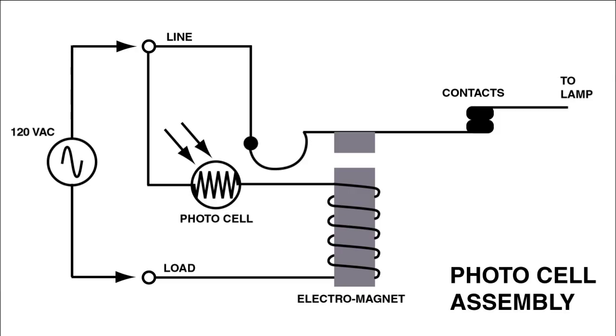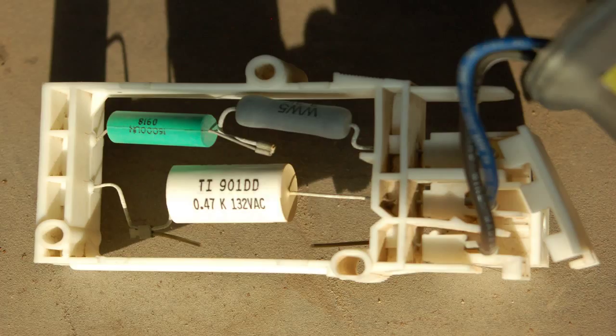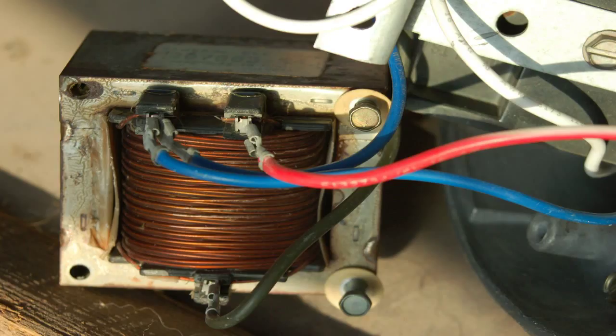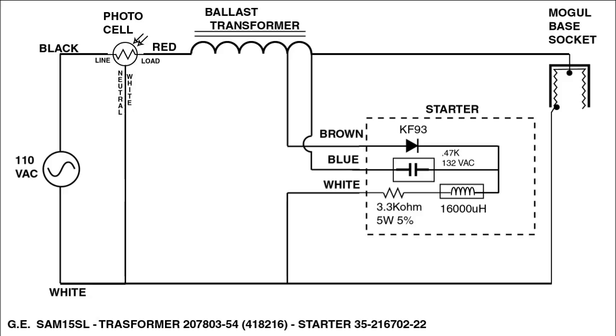If you can eliminate the photocell, then try the starter if you can get one. Most vendors just want to sell you a new fixture, but the starter can be acquired if you dig a little. If the starter doesn't fix it, and you haven't found any broken wires or bad connections in the process, then you can try the transformer. Again, it's not easily available, and they seldom fail. When all else fails, you'll have to bite the bullet and pony up the cash for a new fixture, and they're not cheap. Let's trace through the operation on the schematic.